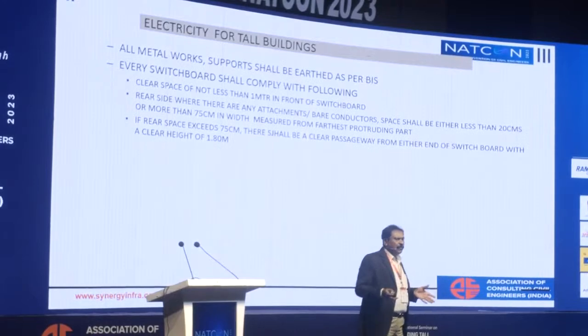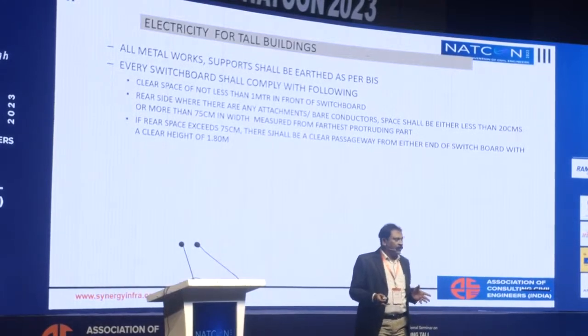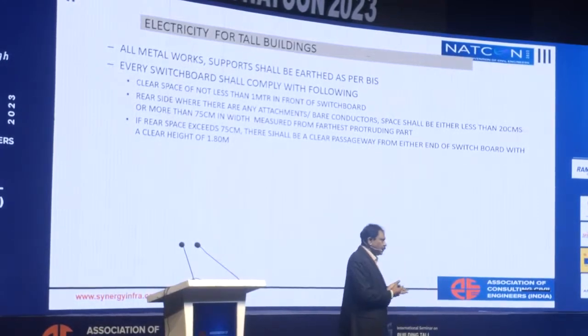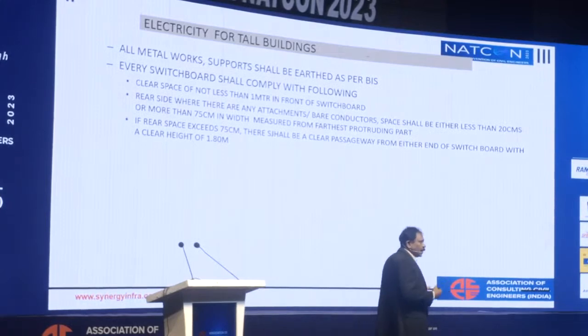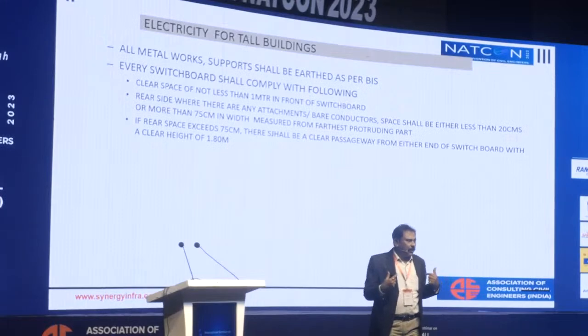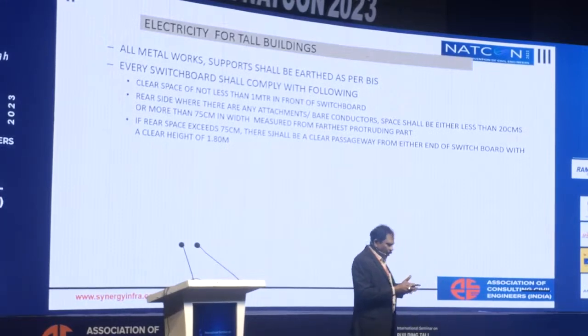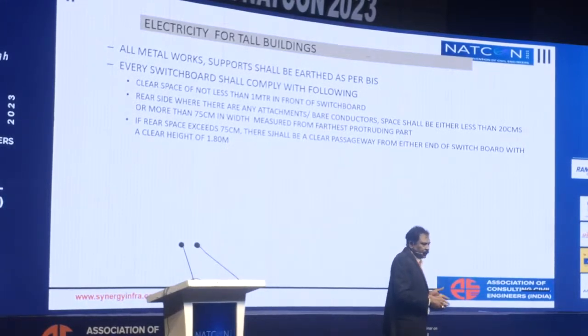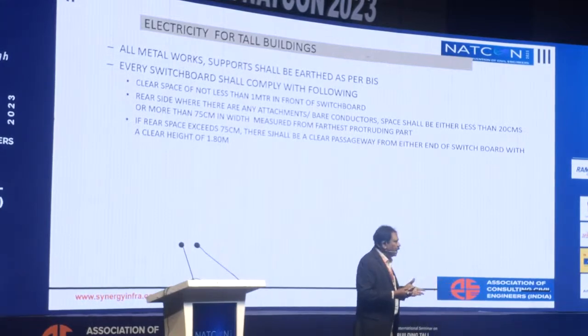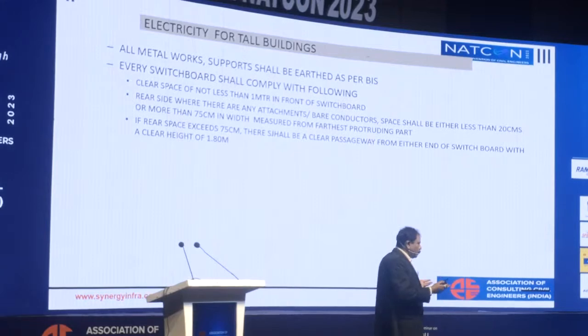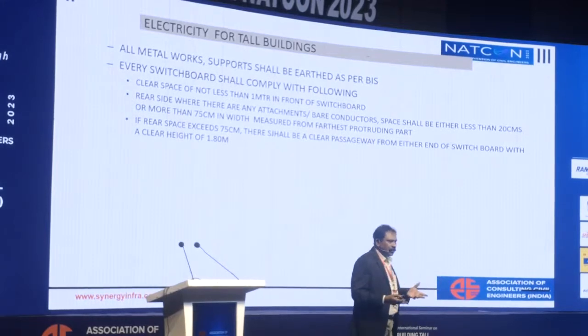And then all metal works inside the building. If you see fire pipelines, water pipelines, which are metal lines, and if you look at hospitals, even your metal doors and windows have to be earthed. And they all have to be earthed to the building earth. The entire building has to be equipotential. There cannot be any potential difference. They all have to be bonded together, and the entire building is used as one earth.